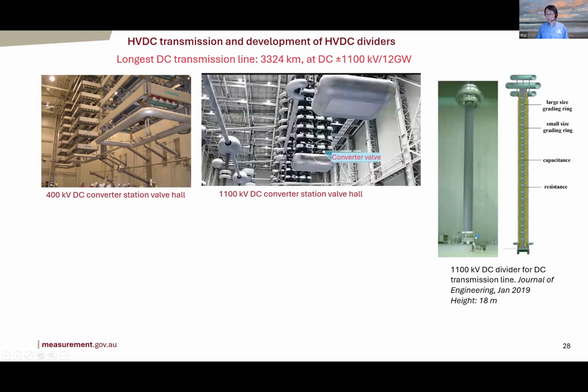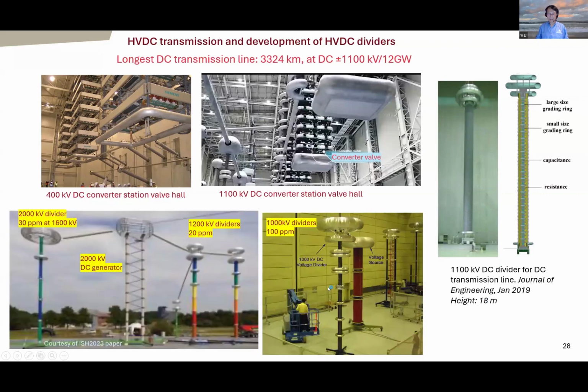And for measurement in the DC network, these are the dividers designed in China, 18 meters high. But NMIs have done a lot of work for reference. And this is the 2000 kV divider, I think PTB, they say, with the Swedish RISE. They achieved a tremendous feat: 30 ppm at 1600 kV, and 20 ppm at 1200. An NMI did some years ago 1000 kV, 100 ppm.